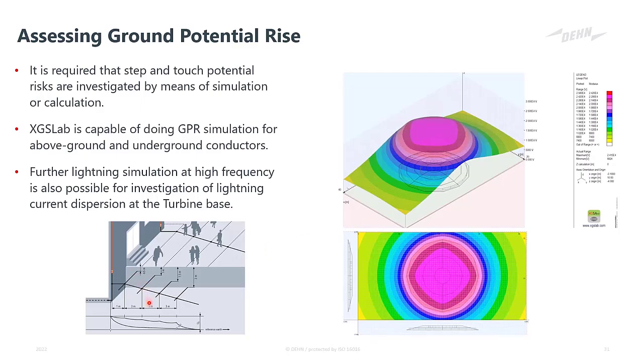If I have someone standing on the soil surface and he steps or stands on two different potentials on this graph, there would be a voltage difference between his feet, and that voltage difference will cause current to flow between the feet, and that can cause electric shock. That's known as step voltage. Now the aim is to get this as flat as possible so that we don't have very large voltage differences, and you can see that it's pretty well achieved in this case, but you can increase this flat area of potential by adding more ring conductors to the system. As you can see here, we start then to control the ground potential rise, and we get that as flat as possible rather than having that cone that we saw in the first slides of voltage on the soil surface, and that just makes it safer.